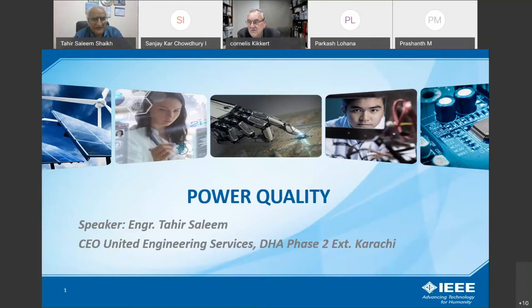In renewable energy also, you need to handle these power quality phenomena very carefully. You have to adopt them very accurately so that, as per IEC 60038, you get a power tolerance limit of plus minus 10%. And as per IEC 61000, it gives you the distortion limits, and the frequency would be plus minus 2%.